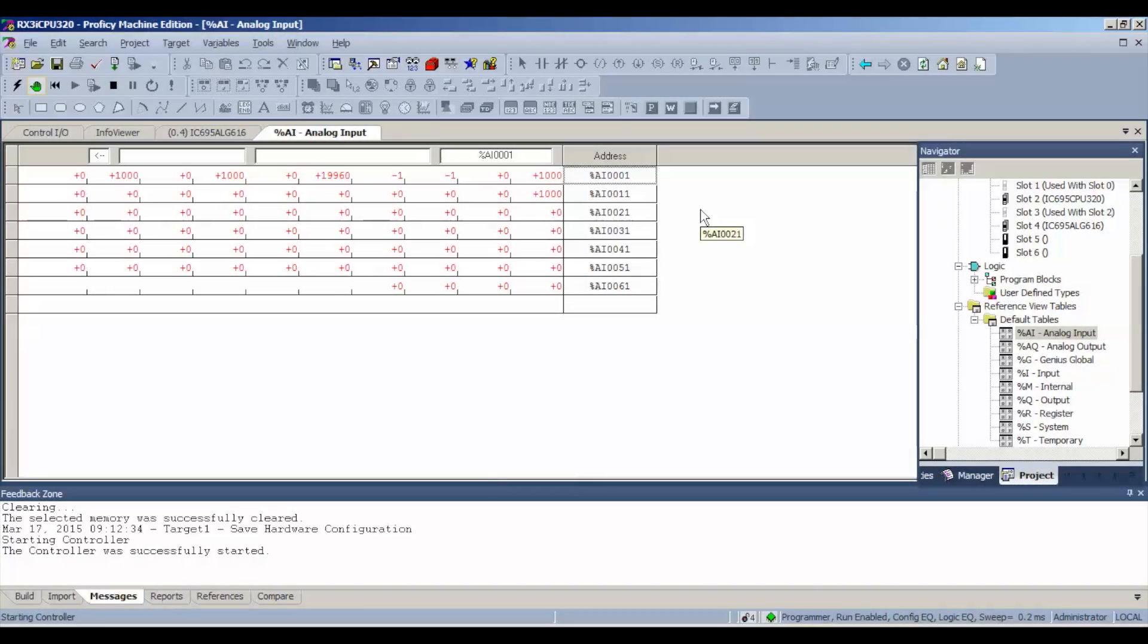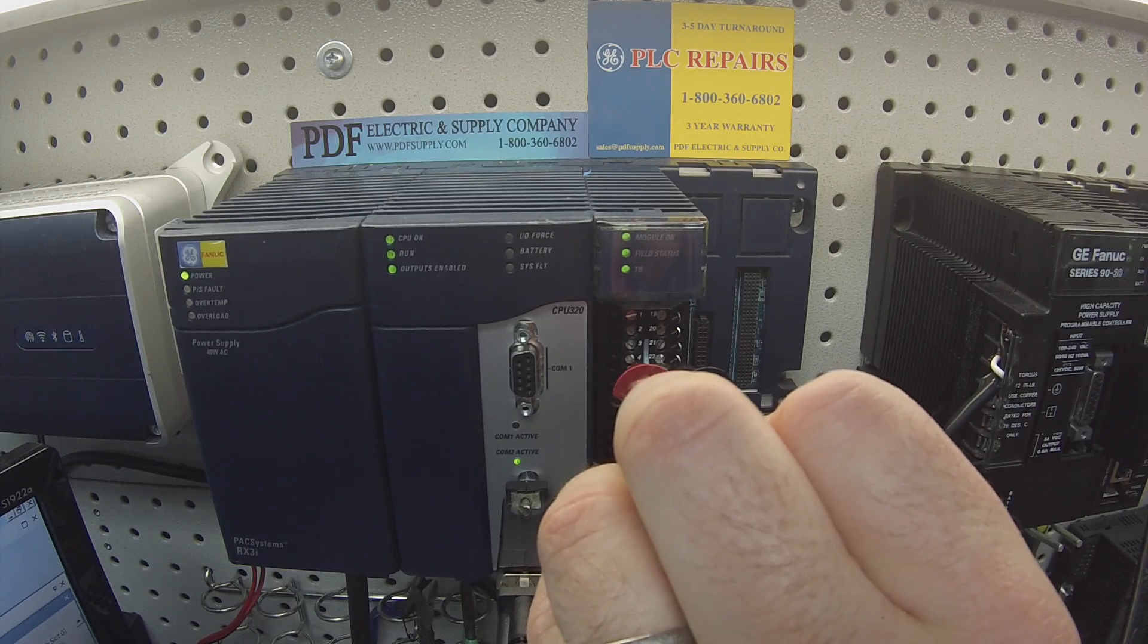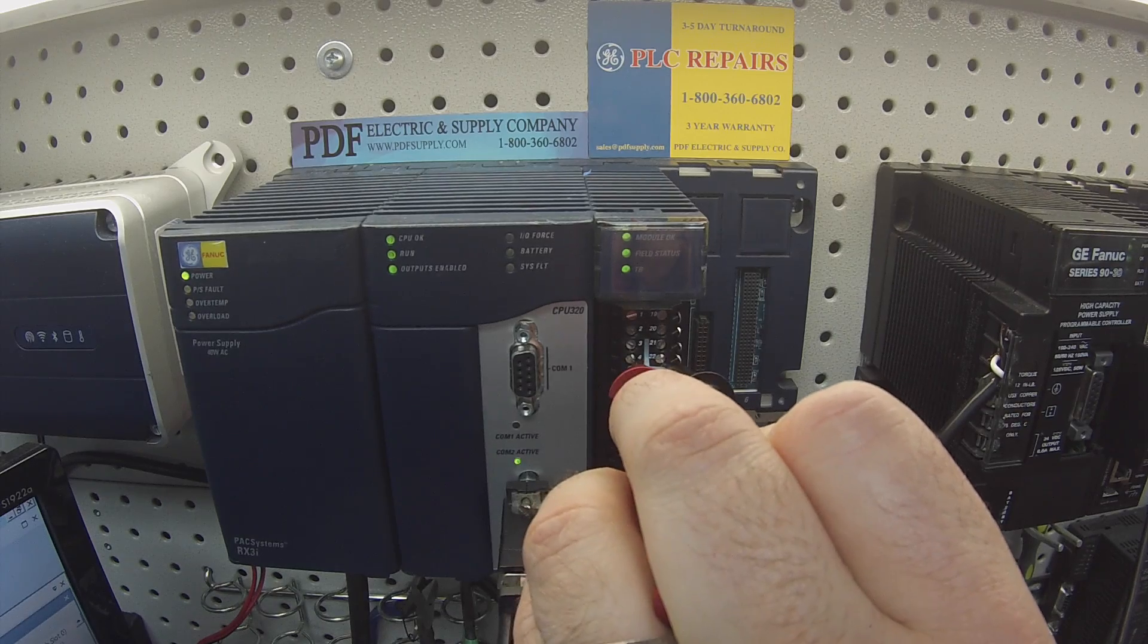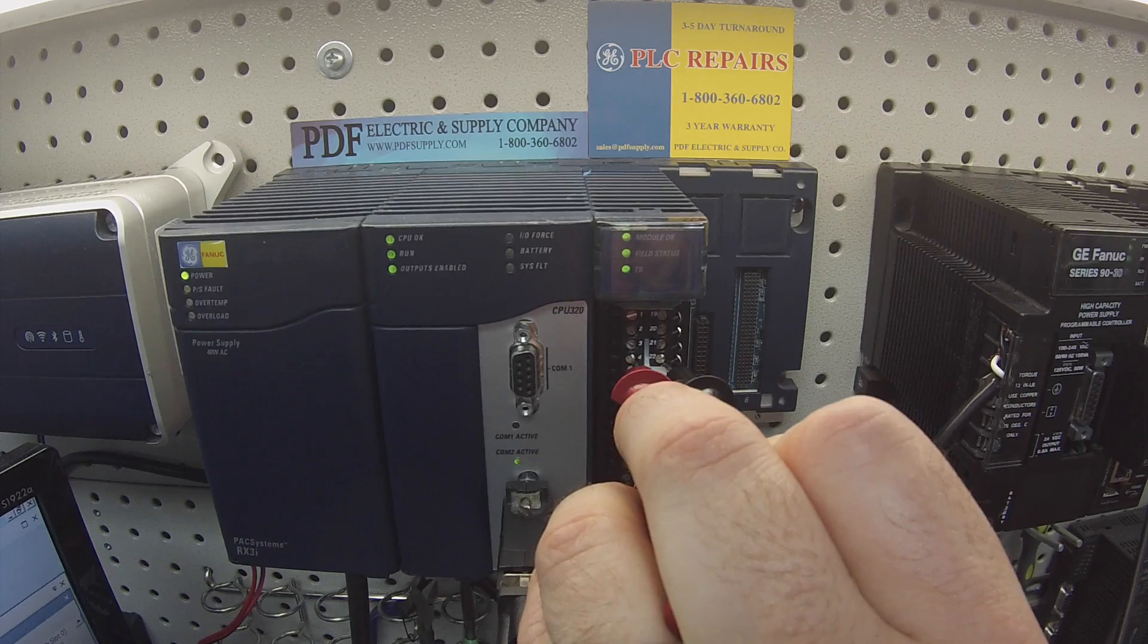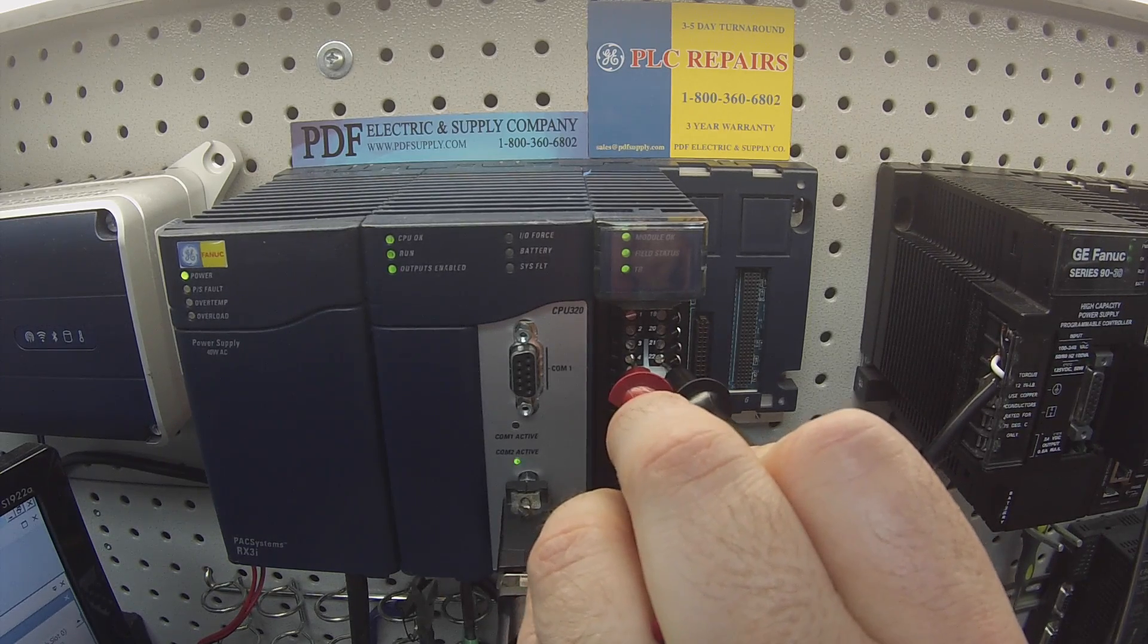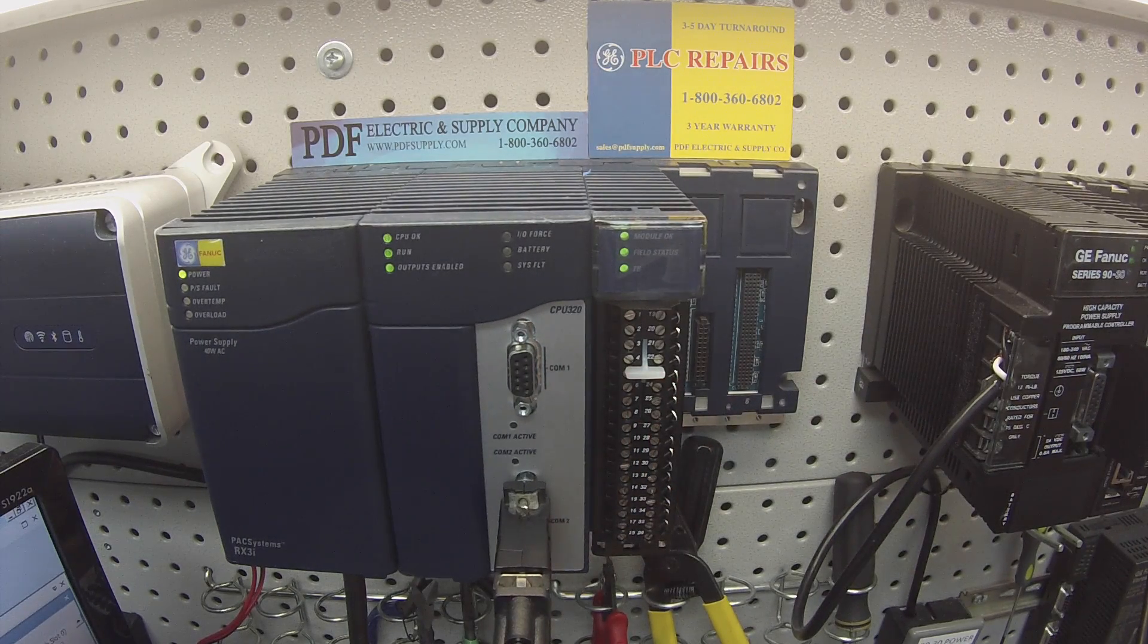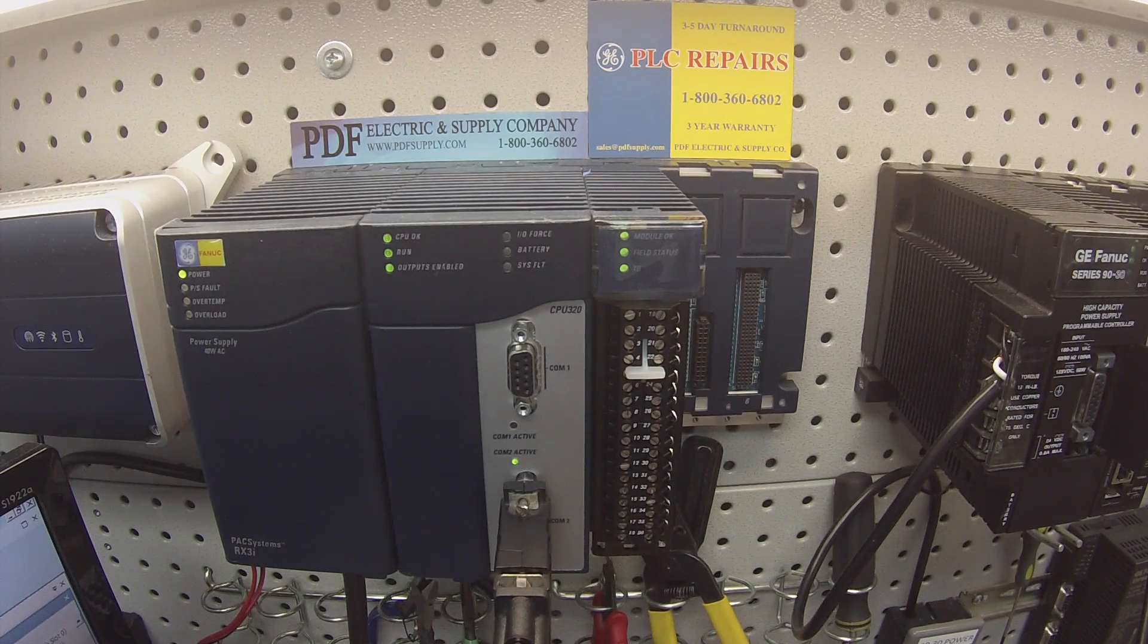And I'm going to continue to dial up and down the values. I'm having a tough time keeping these leads on, I apologize for that. Number three, I'm going to dial down and then back up. A firm connection is really important. As you can see, I'm kind of pushing these probes into these terminals. Another thing you might want to do is screw down the terminals. I notice that if the terminal screw itself is loose, you get a poor reading. So make sure those are down in their lowest position or tightest position. And as you can see, I'm dialing the value down and up and so on. Now if I was testing this card in our lab from a customer, I would test all 16 channels the exact same way. I would check the full range and resolution and I would look for all the problems I mentioned before.